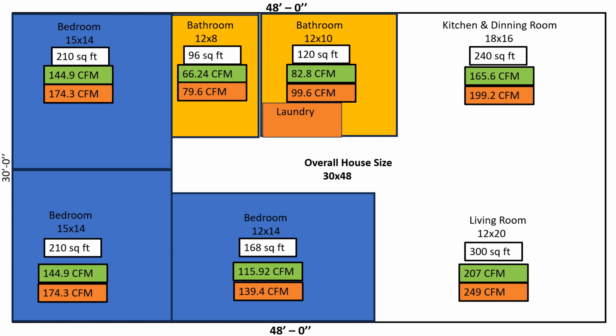So this is just an example to give you an idea of what you need to do. But I wanted you to just see that by changing from a 2.5-ton to a 3-ton unit, how much CFM that room is now going to take. Now you look at it, and there's quite a bit of difference.